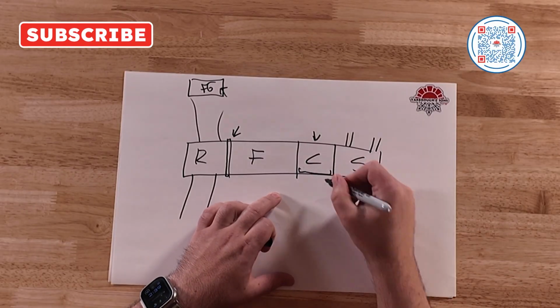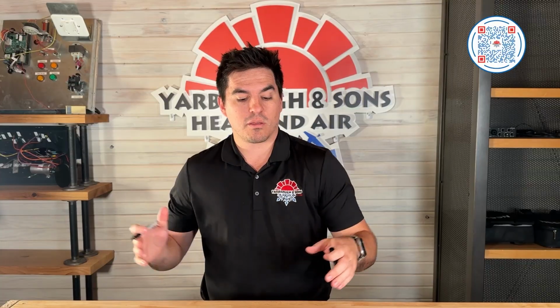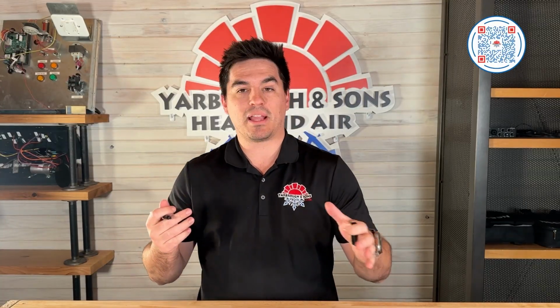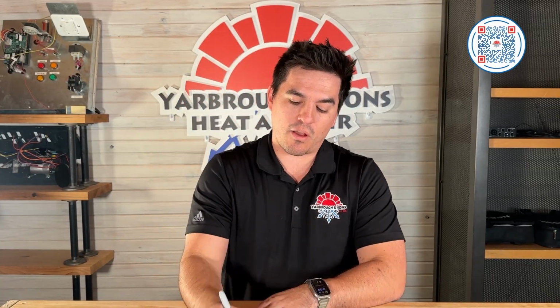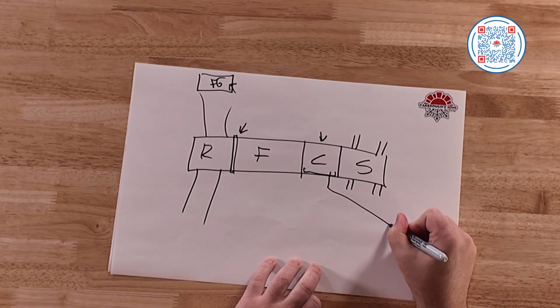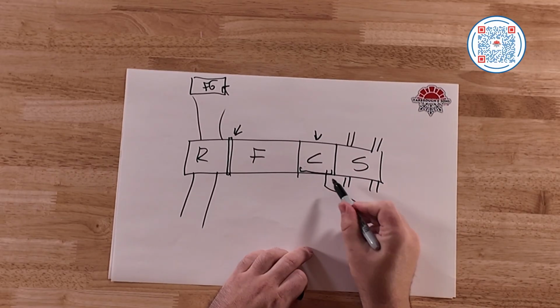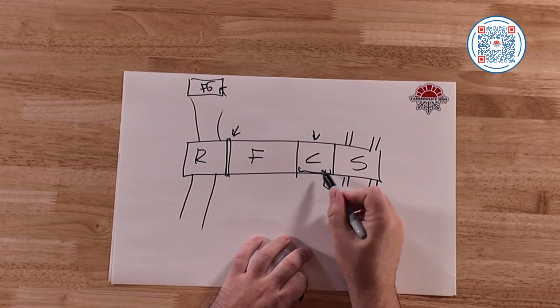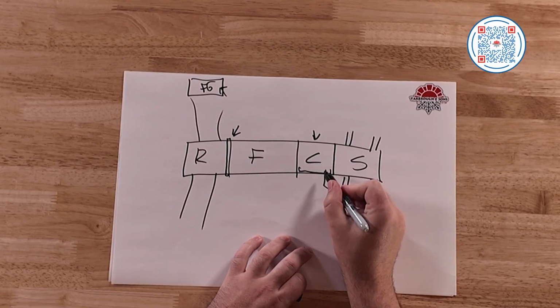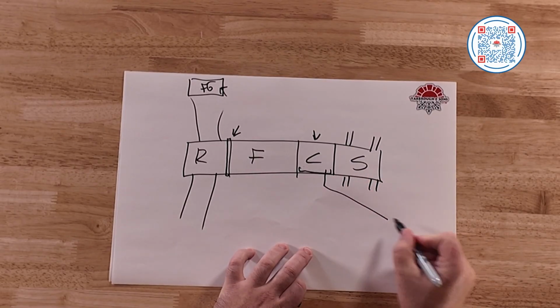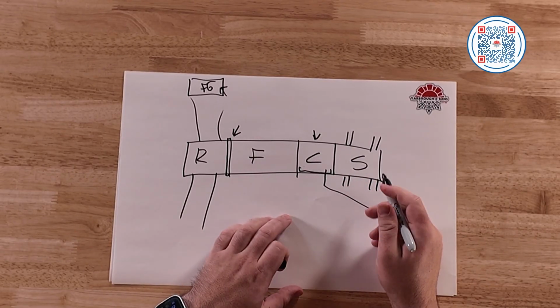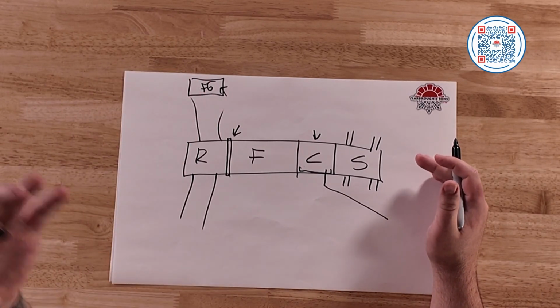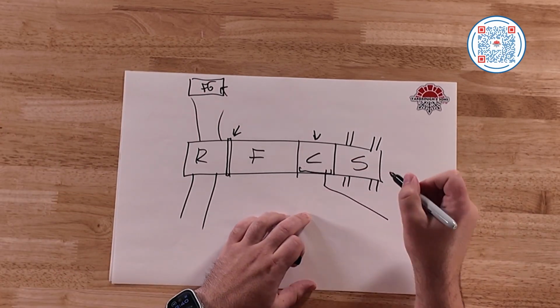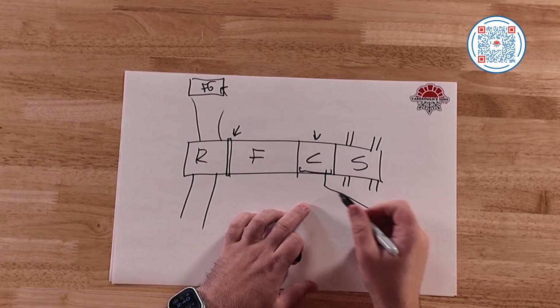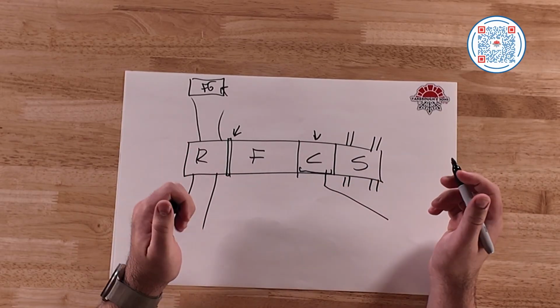Some things to do, if you're smelling that smell that's smelly, is to make sure, one, that your condensation drain line is clear. Your condensation drain line is the exit for all the water that your evaporator coil produces. If this line gets clogged up in any way, shape, or form, and it gets clogged because there's maybe an excess of debris, you want to make sure that it is completely clear, and then make sure your pan is also clear of debris as well.